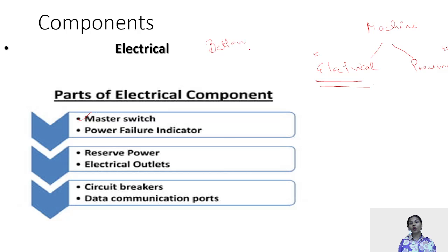or your electrical outlets that are present on the machine. And one more interesting thing, which will be coming in detail in your intermediate pressure system also: the only pneumatic component of the whole machine which is independent of the master switch is your oxygen flush. Please remember this right now. We'll again come to this concept. But the only pneumatic component which is independent of the master switch is your oxygen flush, which is an emergency aid.